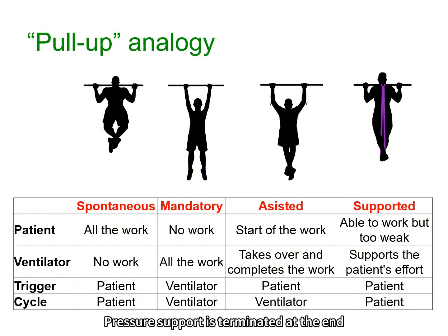Pressure support is terminated at the end of each spontaneous breath when the flows start to decrease. It is different from an assisted breath, which is forced on the patient regardless of the natural duration of the breath. Hence, the ventilator in supported ventilation mode can cooperate with the patient better than in assisted mode.